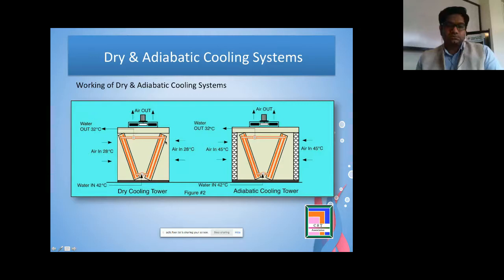But the problem in the dry cooler comes when the ambient temperature goes above 28 degrees centigrade. Let's say at 28 degree air in and 32 degree water out, our approach of the cooling is 4 degrees centigrade. The moment this temperature becomes 29, 30, 31, 32, these coolers will not be effective. Even if we change from 28 to 29 degrees centigrade, we will require a very large surface area to avoid this. So what we can do is use pads.